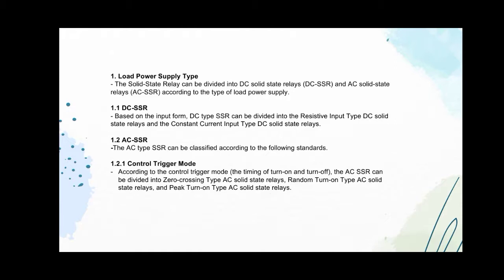Based on the input form, DC type SSR can be divided into resistive input type DC solid-state relays and constant current input type DC solid-state relays, as I mentioned in the load power supply type. And the other one is AC SSR. The AC type SSR can be classified according to the following standards. Control trigger mode: according to the control trigger mode, which determines the timing of turn-on and turn-off, the AC SSR can be divided into zero crossing type AC solid-state relays, random turn-on type AC solid-state relays, and peak turn-on type AC solid-state relays.